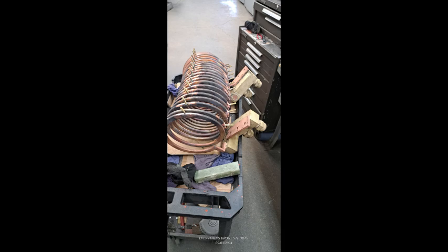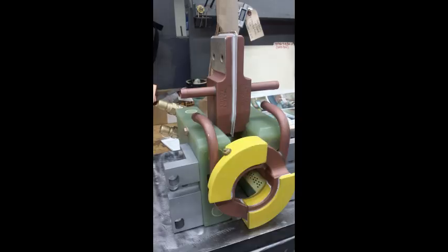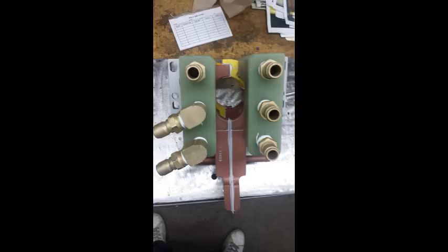Understanding induction heating coils and processes. Induction coils can form tunnels for parts to pass through, ideal for high-speed production. Operating frequency: lower frequencies heat deeper, higher frequencies heat shallower. Thermocouples: K-type thermocouples monitor temperatures up to 2,000 degrees Fahrenheit, properly attached for accuracy.